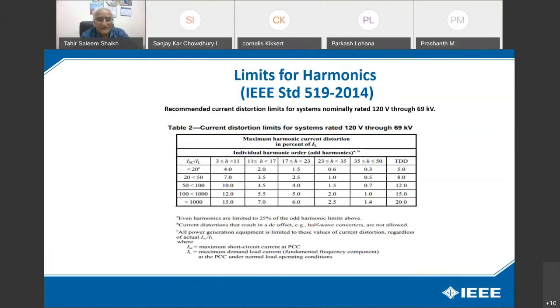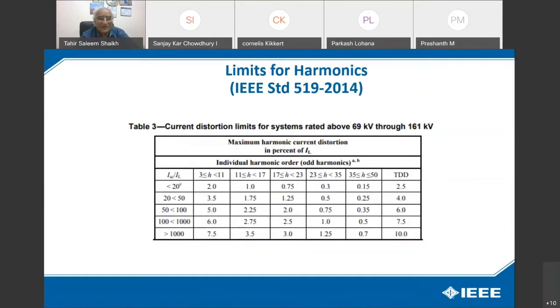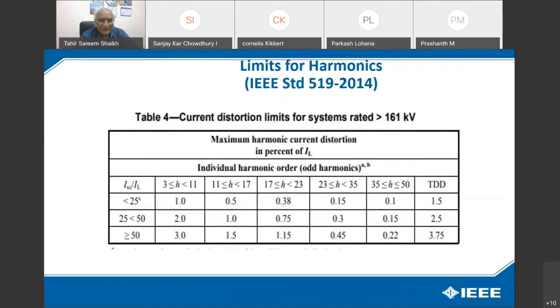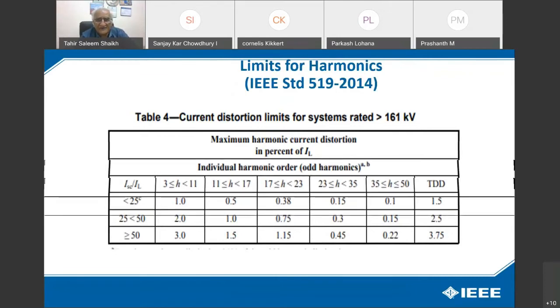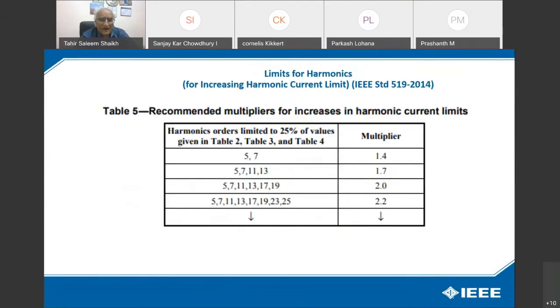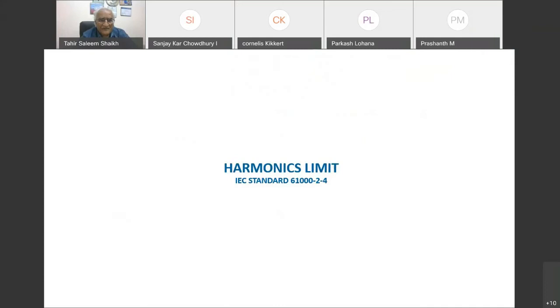So you have to operate either as a renewable energy or conventional energy within these limits, so as to avoid any defects in the equipment. Maximum harmonic current distortion, what should be there? So this is the ratio given over there, distortion in percent of IL. So we give you the chart. Maximum harmonic current distortion percentage of IL, total current distortion limit for system rated high voltage. Harmonic order limit 25% of the value given in table 2, table 3, and table 4 for that particular standard and codes.